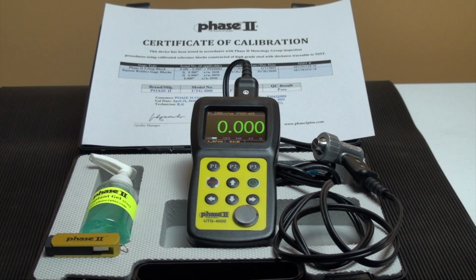Generally, velocity of sound through the material to be tested is a known value and is supplied via chart in the operation manual. In the case of the UTG-4000, we have preset the unit velocity to read in steel, which matches the material of the built-in test block. You always have the option to manually preset the velocity of any material.